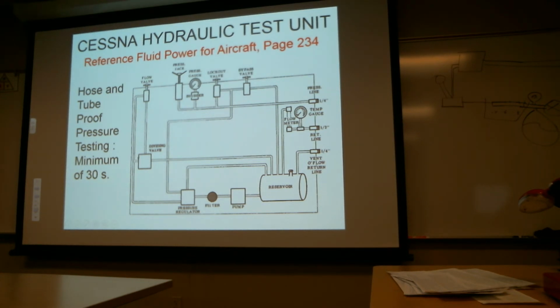This also has a temperature gauge. Sometimes if you know the trend in a hydraulic system, you can make inferences on malfunction. If the temperature is higher than it should be, it may indicate a pump is wearing itself out, or there might be excessive friction of some component.